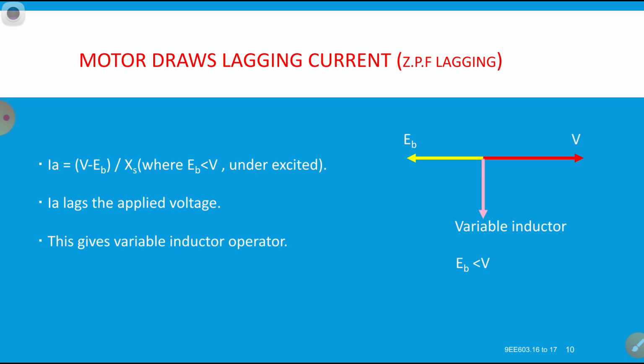If you use these reactive power reactors in substations, and even then the receiving voltage is not up to the level, the terminal receiving voltage is more than the sending voltage. Then what to do?